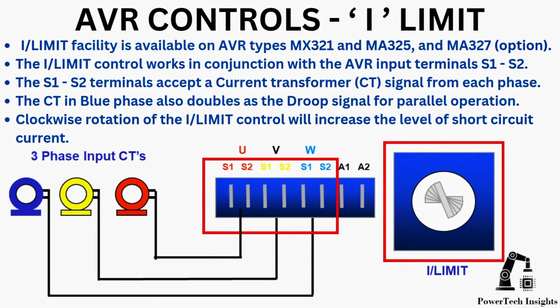AVR controls, I-Limit. I-Limit facility is available on AVR types MX321, MA325, and MA327. The I-Limit control works in conjunction with the AVR input terminals S1, S2. The S1, S2 terminals accept a current transformer (CT) signal from each phase. The CT in the blue phase also doubles as the droop signal for parallel operation. Clockwise rotation of the I-Limit control will increase the level of short circuit current.